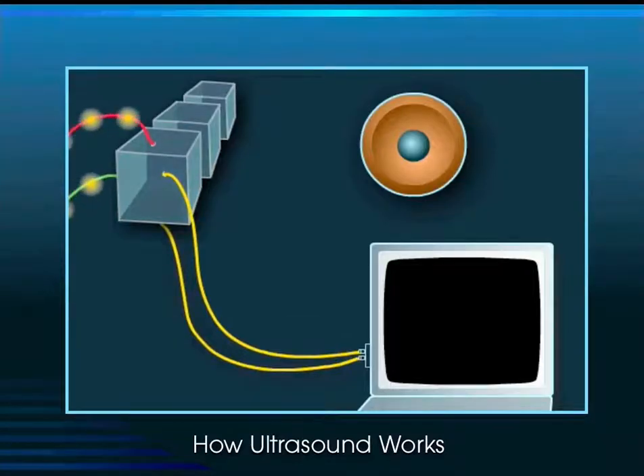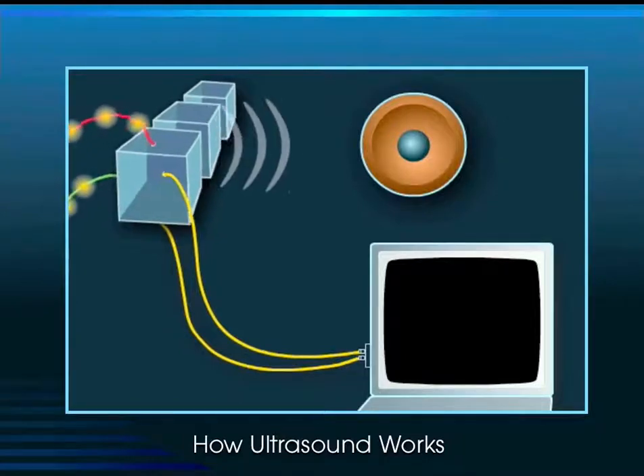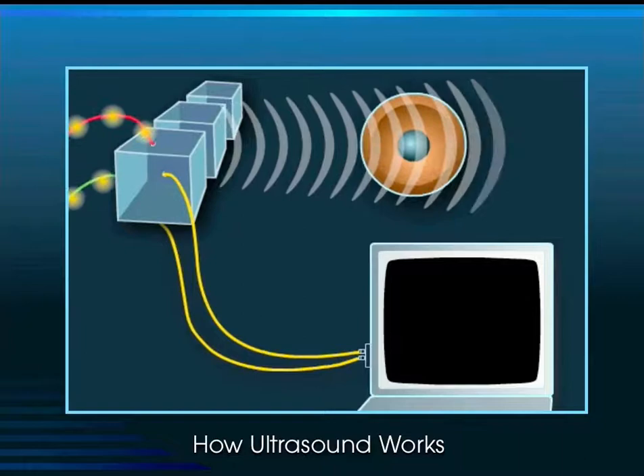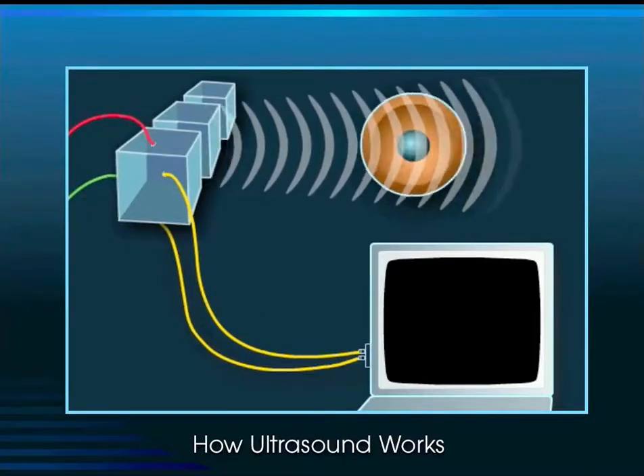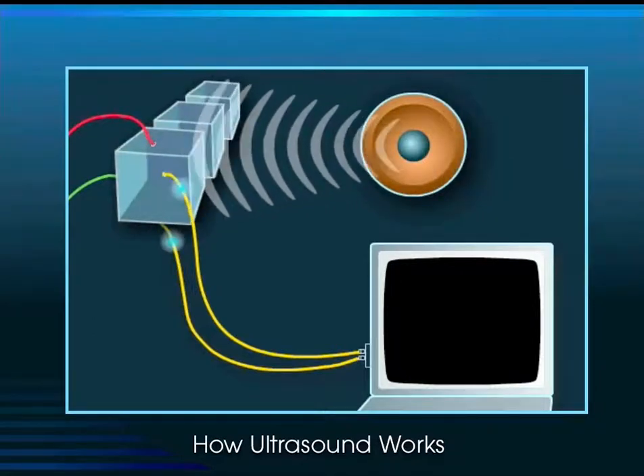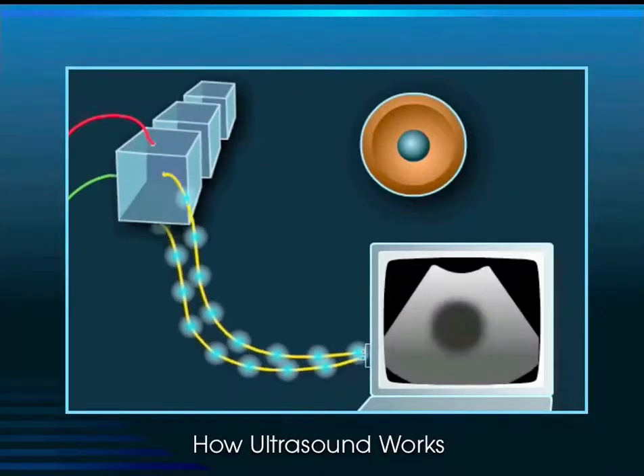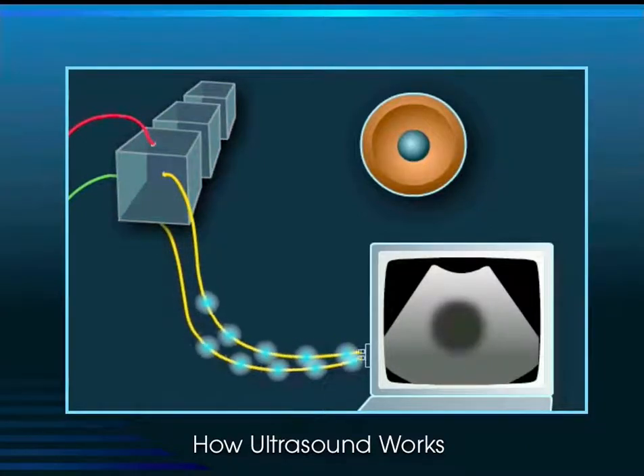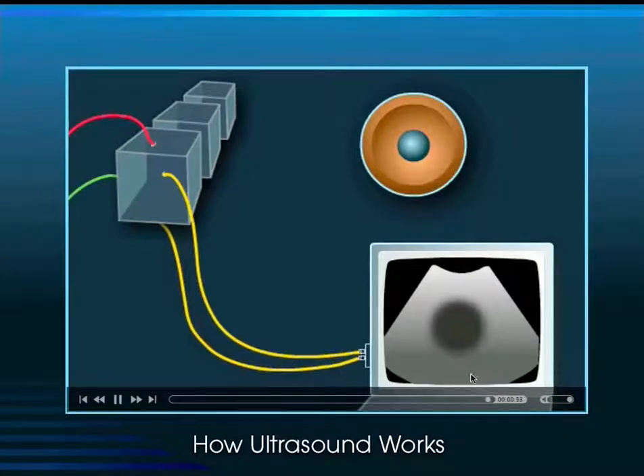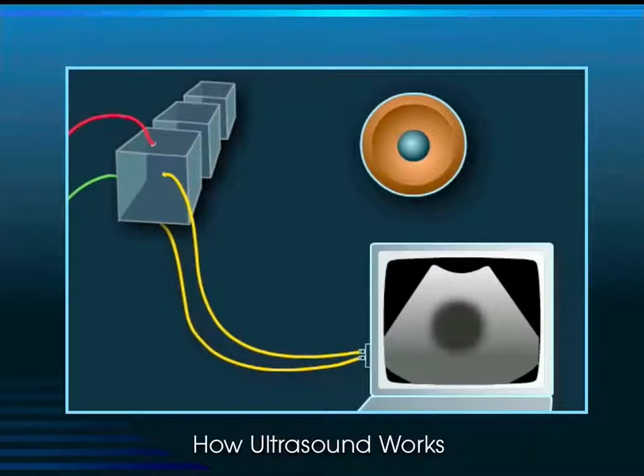Ultrasound works via the piezoelectric effect: when electricity is applied to the transducer, the crystals shake and sound is emitted at the ultrasound frequency. Those sound waves travel into the body, reflect back to the crystals, and the crystals shake again, transducing acoustical energy back into electrical energy. The machine plots these dots on screen — the longer it takes sound to return, the further down the field the dot is plotted. The denser the tissue, the more echo-bright the dot; the less dense (such as water, urine, or bile), the darker the dot.